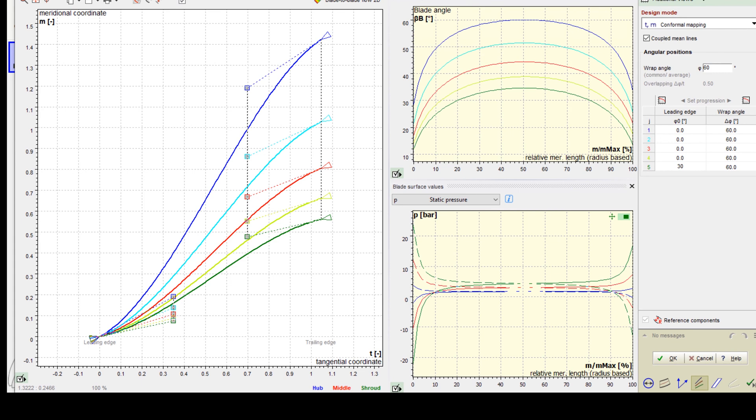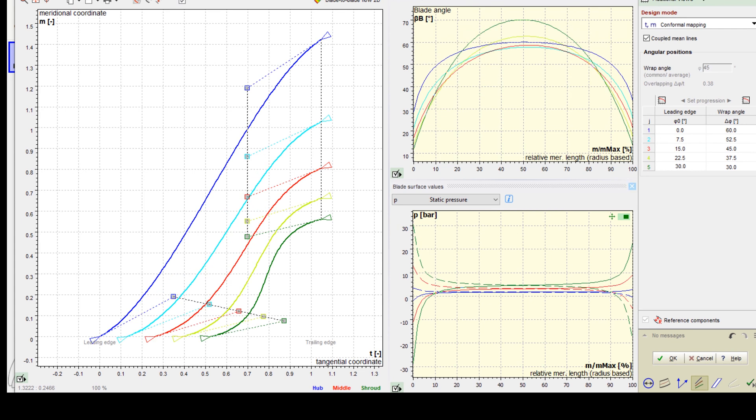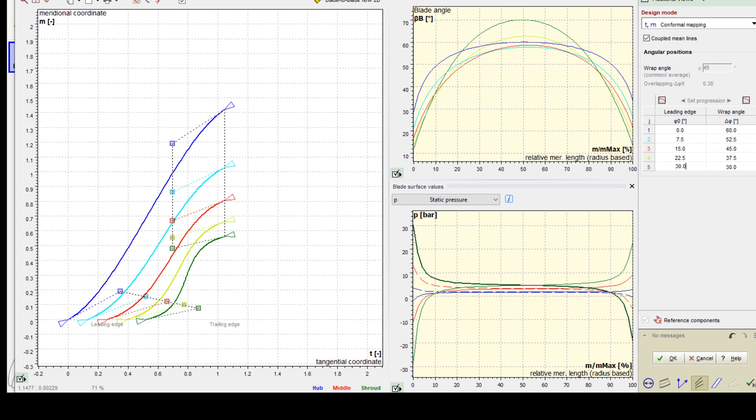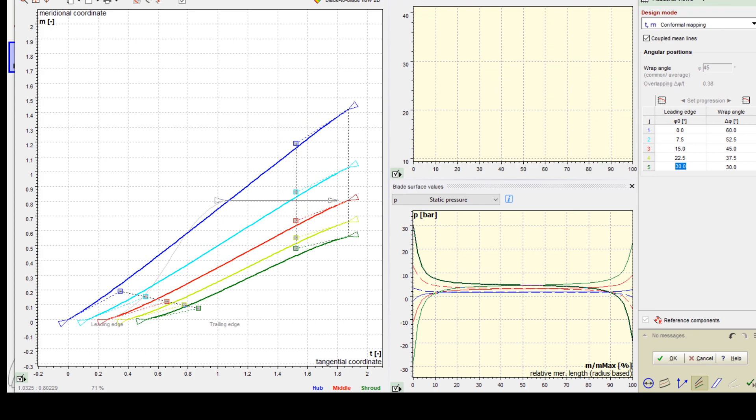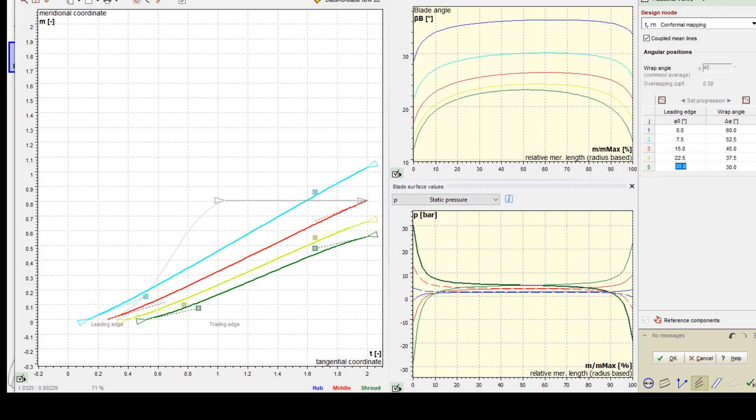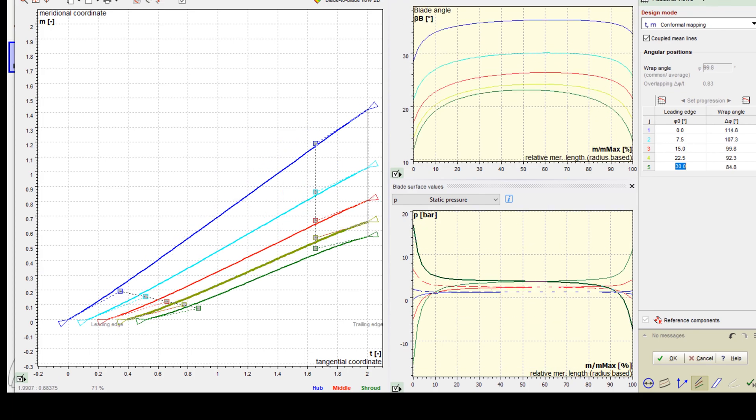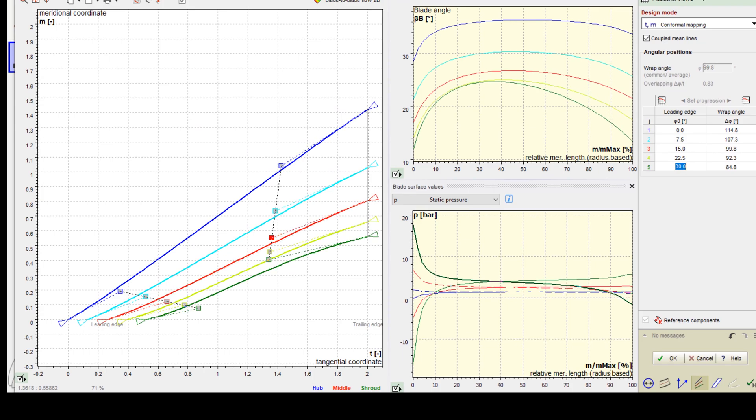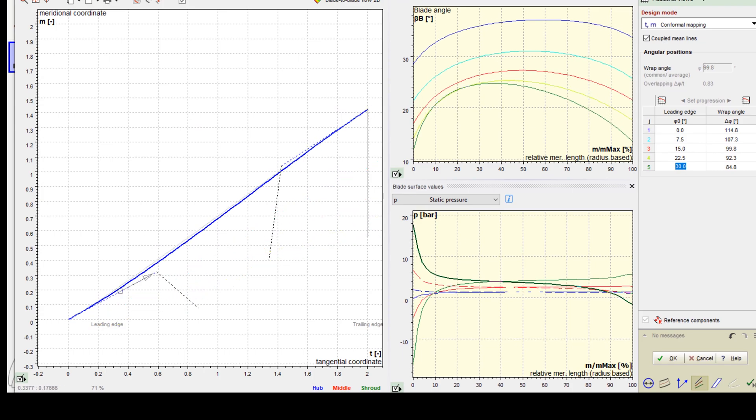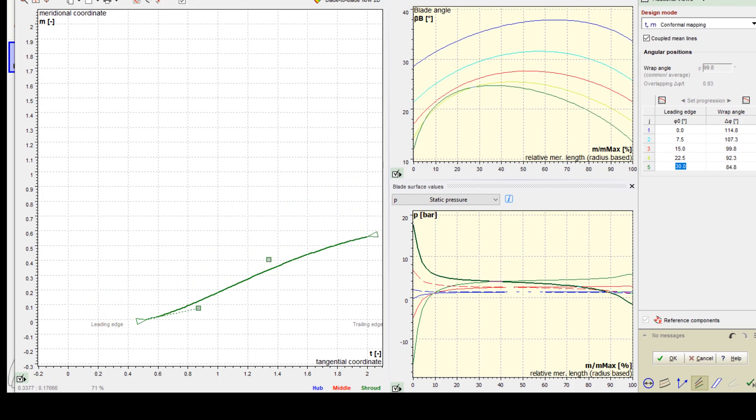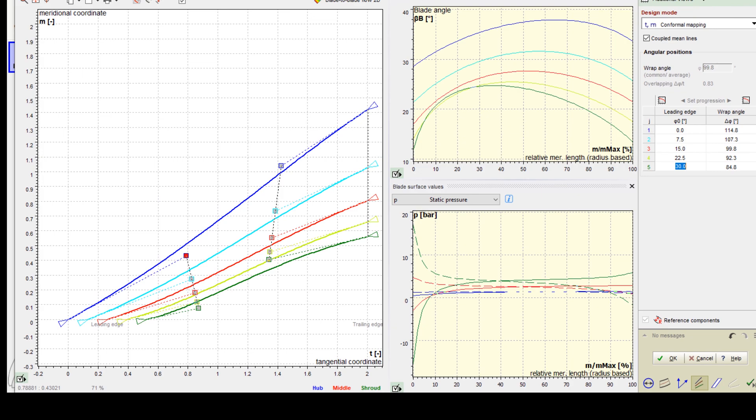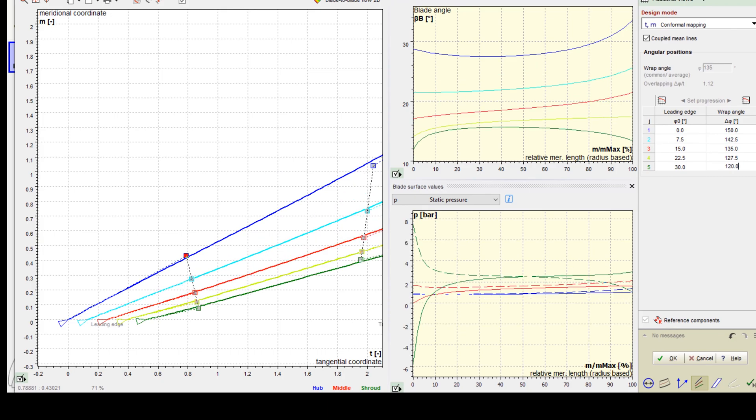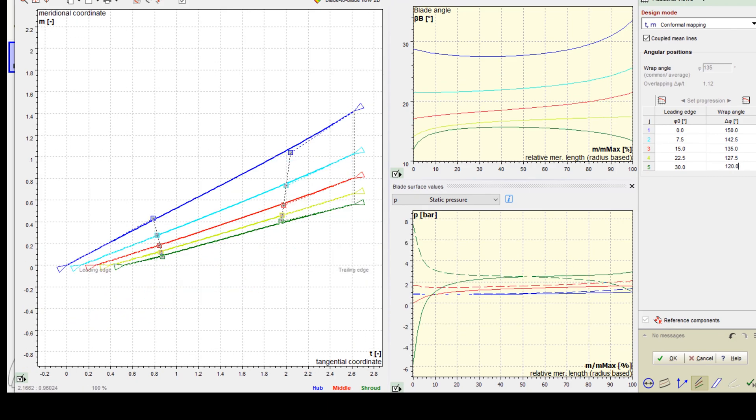In the next design step, we do the mean line design, which determines the curvature of the blade between leading and trailing edges on every span. Mean lines can be coupled or uncoupled. The curvature and the wrap angle of the blade can be adjusted graphically or numerically. On the right side of the window, we have several diagrams to evaluate geometrical and physical properties like blade angle distribution, area progression, lean angle, and static pressure.